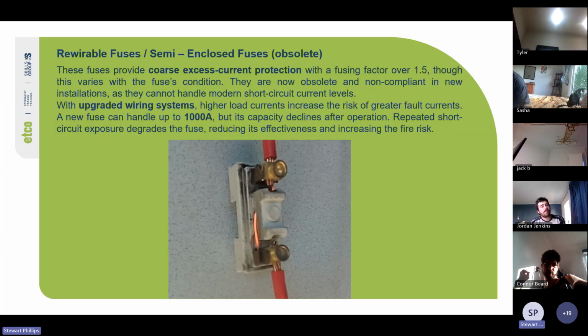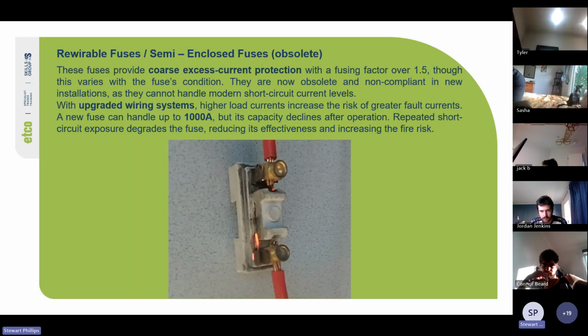Cool. So these fuses provide coarse excess current protection with a fusing factor over 1.5, though this varies with the fuse's condition. They are now obsolete and non-compliant in new installations as they cannot handle modern short circuit current levels. With upgraded wiring systems, higher load currents increase the risk of greater fault currents. A new fuse can handle up to 1,000 amps, but its capacity declines after operation. Repeated short circuit exposure degrades the fuse, reducing its effectiveness and increasing fire risk.